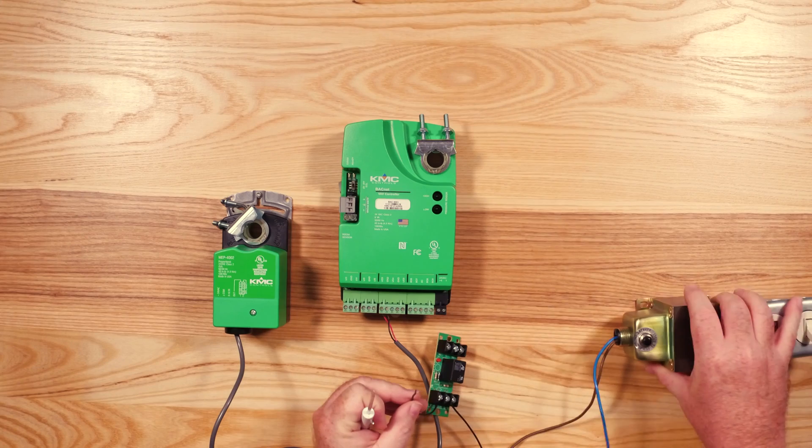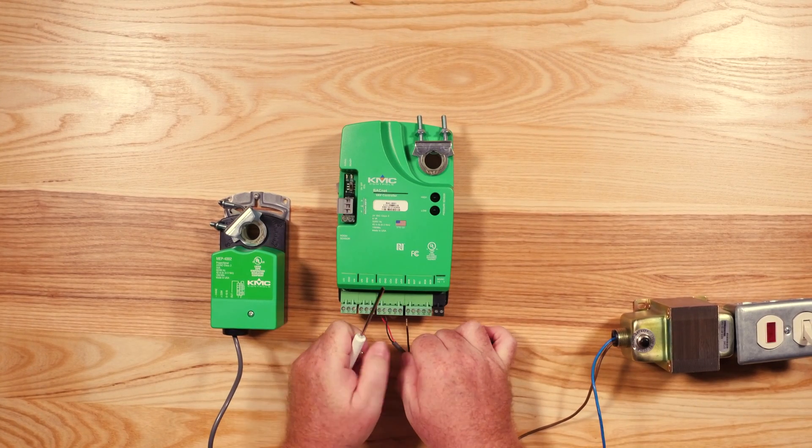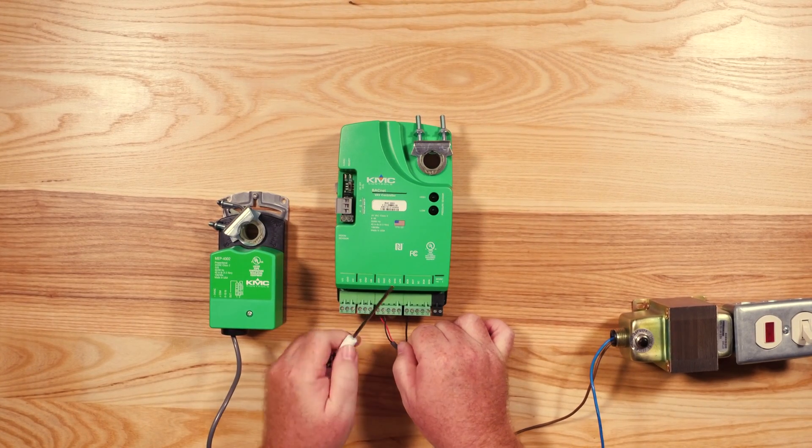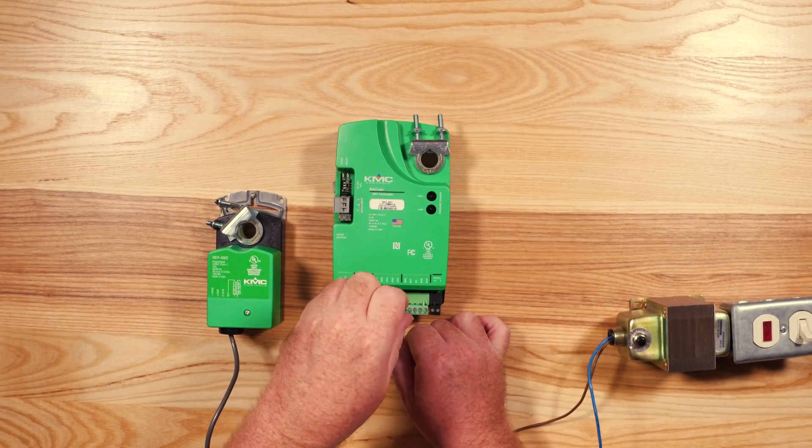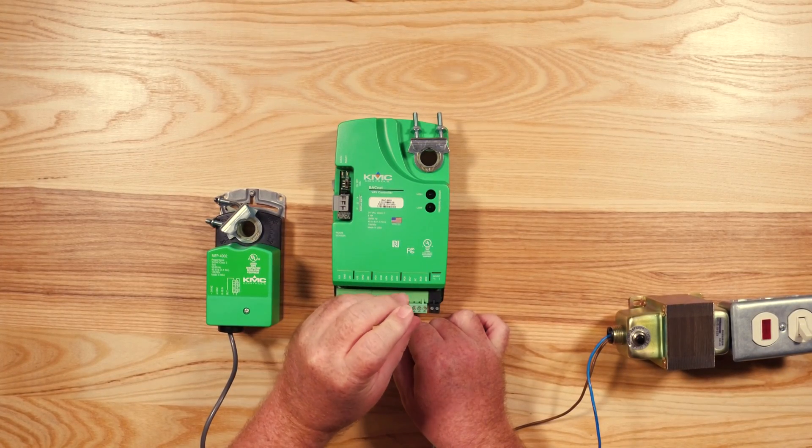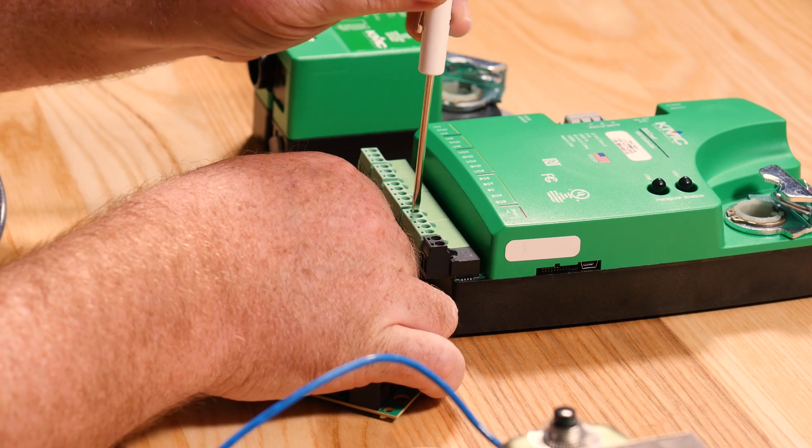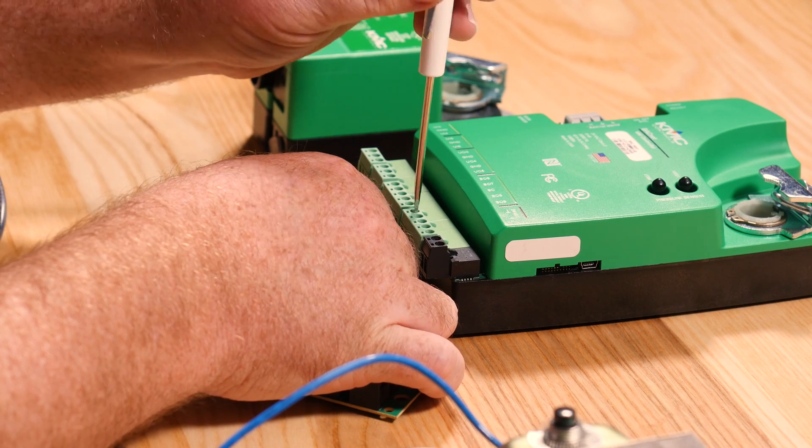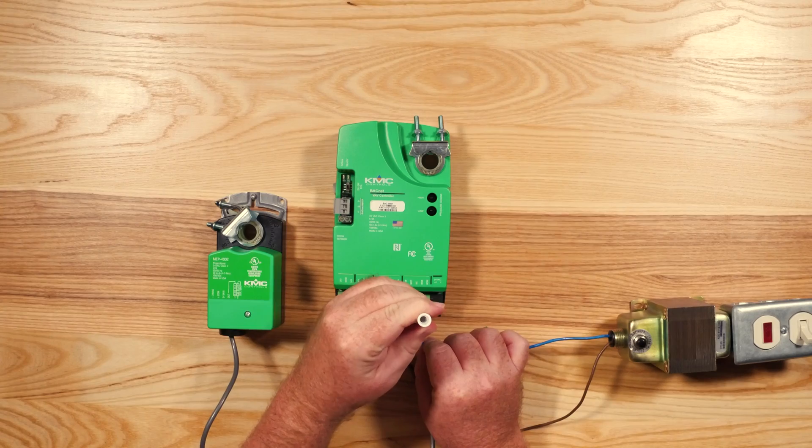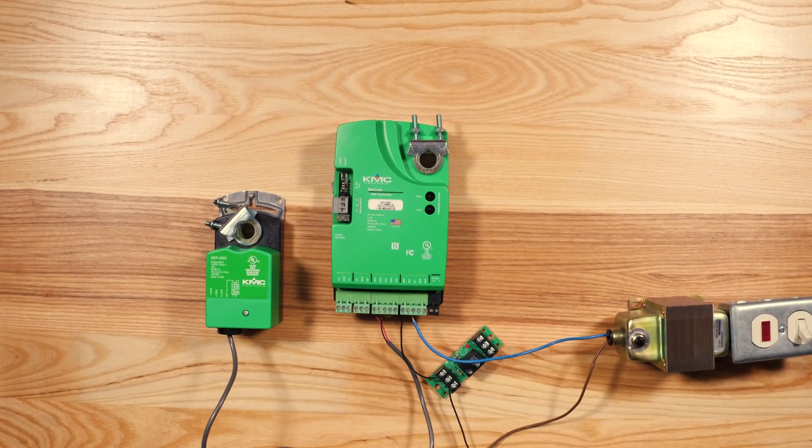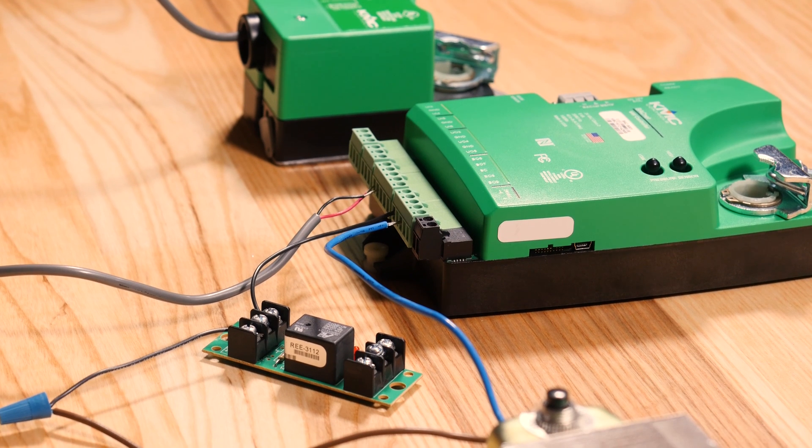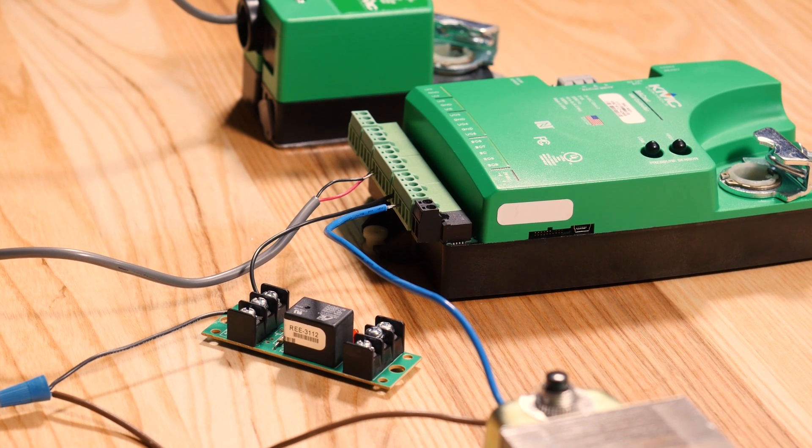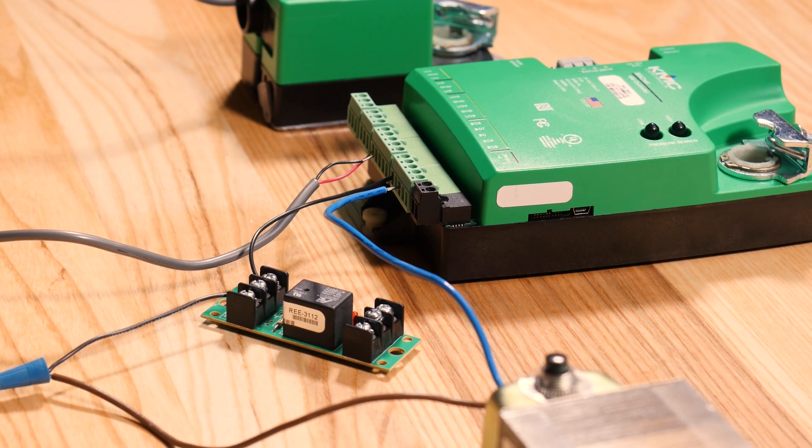Unlike universal outputs, the binary outputs have an internal TRIAC configuration requiring the switched common port to be supplied 24 volts from the transformer. Your signal wire goes out from the BO terminal to the device appropriate for its application. The common wire can then be grounded to the common terminal of the same transformer supplying power.